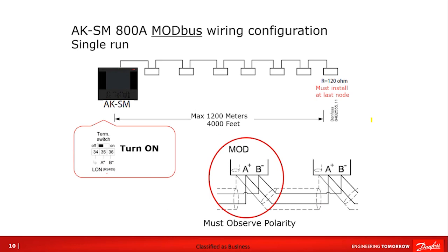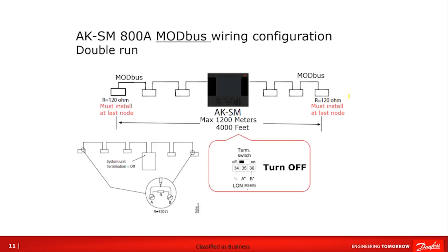Modbus wiring is essentially the same. Polarity must be observed — A and B from one device to the next. Termination: if the System Manager is at one end, that termination switch needs to be in the on position, and also at the device on the far end. Similarly, we can place the System Manager in the middle of the loop with termination off at the System Manager and resistors at either end — one way to combine two communication loops into one.